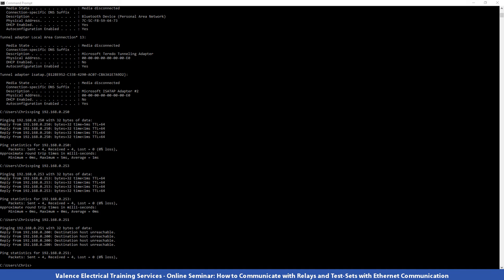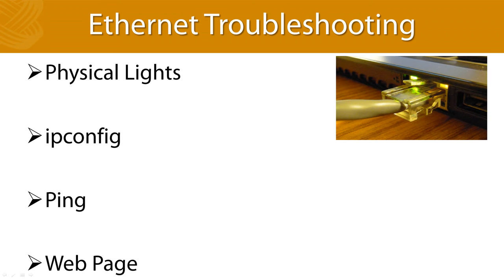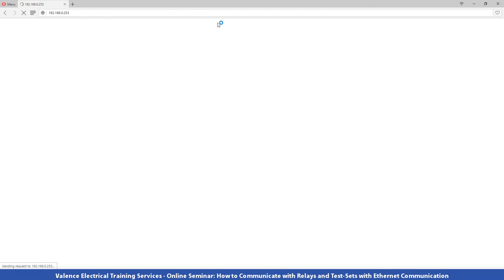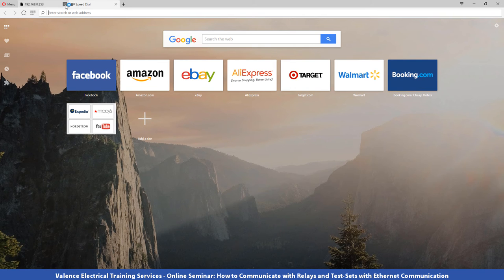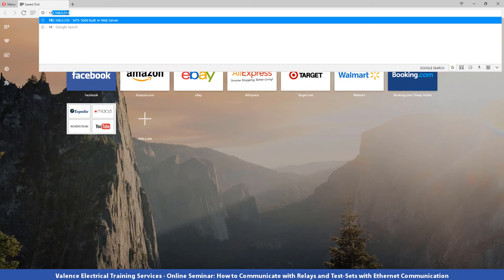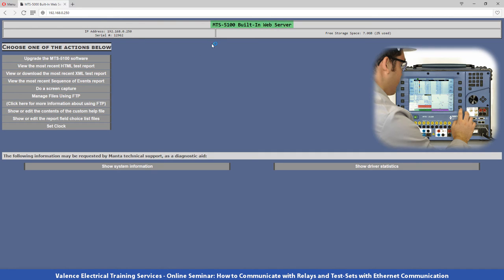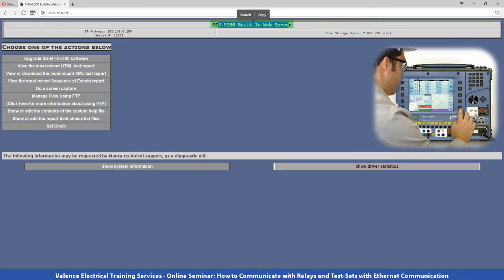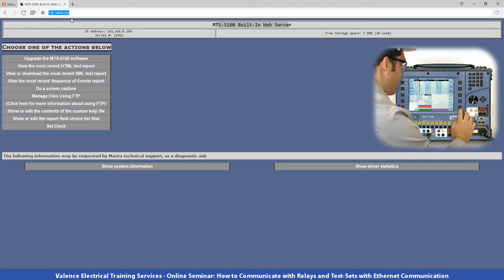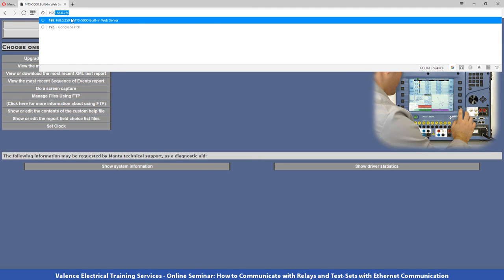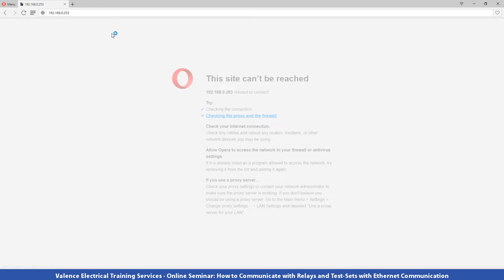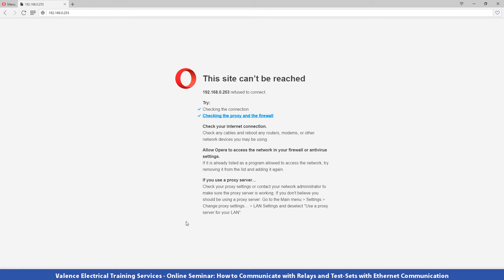Pinging isn't perfect, however, because it happens underneath the operating system. You could get a perfect ping, but your IT department can still block communication via Windows. The ideal solution is when the device you're communicating with has a built-in web server. You can test the connection by opening up any browser. I'll open Opera in my case and I'll type in the IP address of the device I want to talk to, which is 192.168.0.250. And I'm connected to an MTS-5100 and it has a built-in web server, so I have something that makes sense for the device I'm trying to connect to. I'm also connected to an ABB relay and ABB has told me that some of their relays do have built-in web browsers. So if I type in 192.168.0.253, if I see something that says ABB, then I would know that I'd be able to communicate with any Windows program if I saw that come up. This relay must not have that internal browser inside of it.